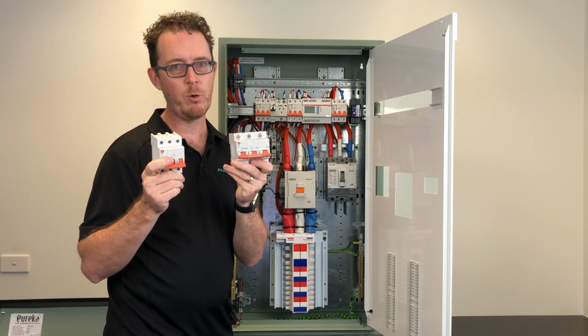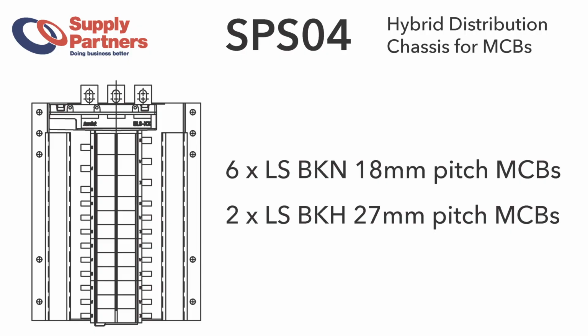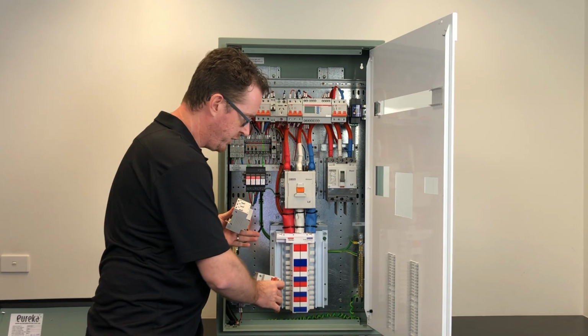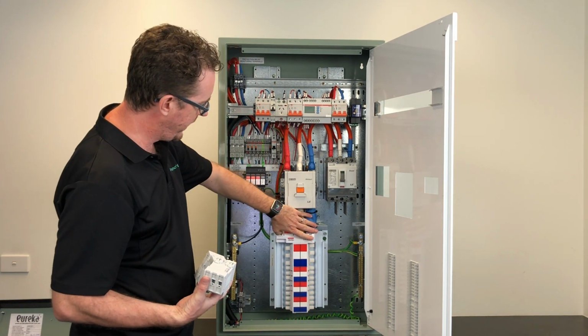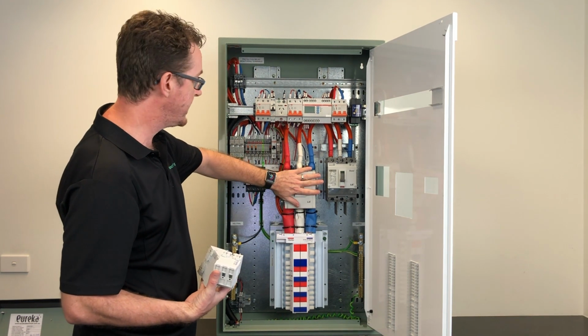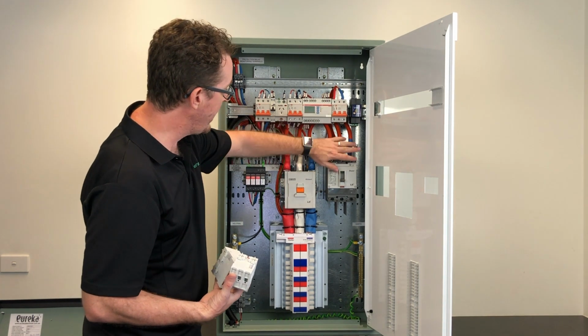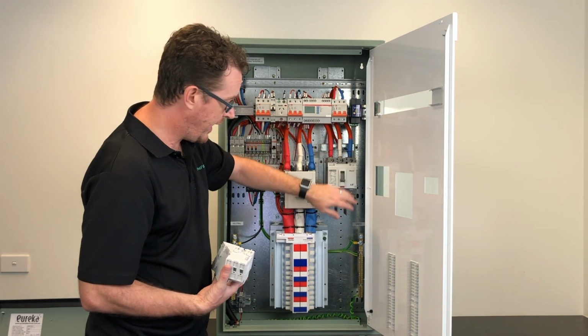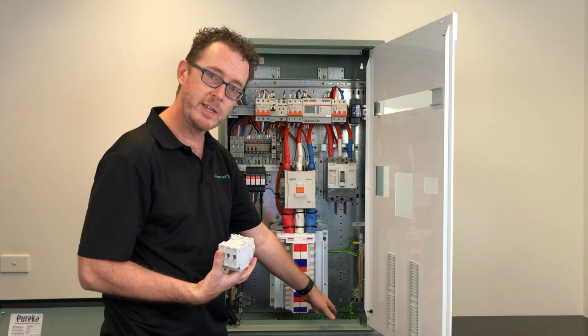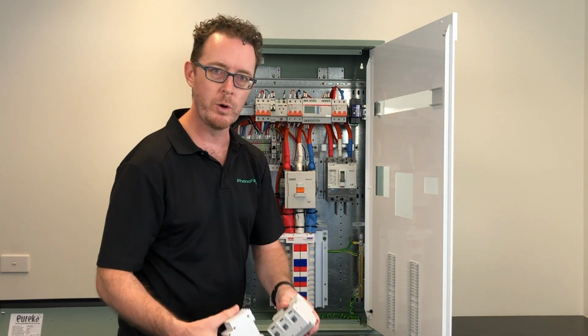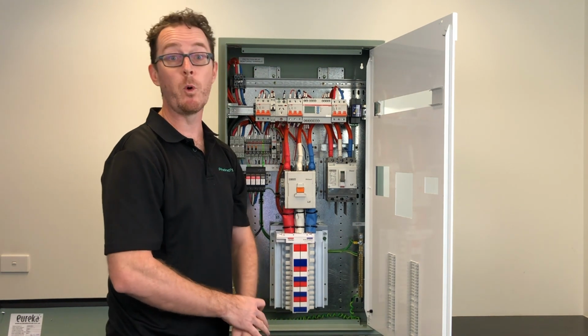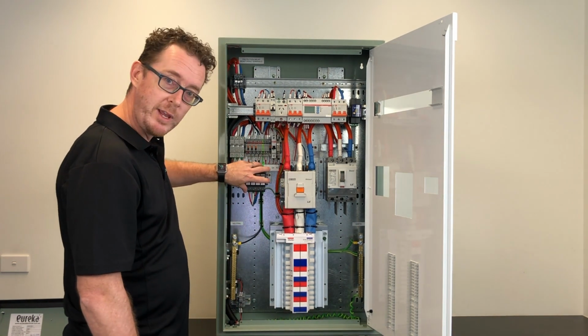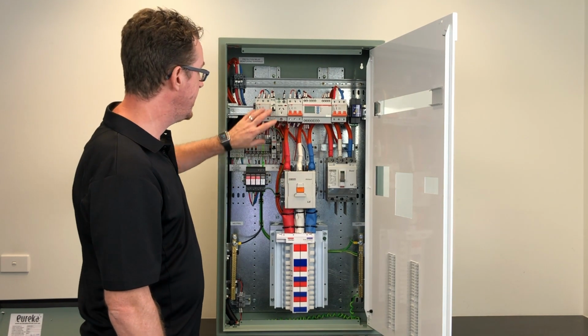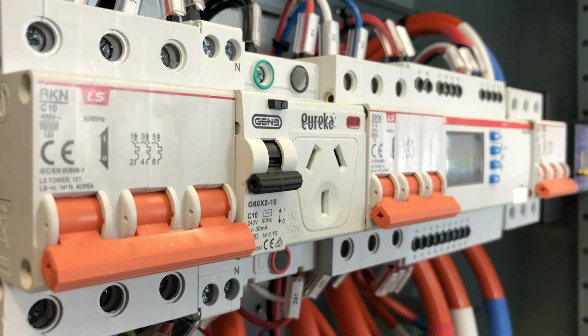All of these different configurations are achievable using the distribution chassis, where the circuit breakers go straight onto the fingers here. And then you can see that we have the busbars up to the contactor. They flow through around to the main isolator, and then from here you have your AC feed to your main switchboard, or the switchboard that you're connecting to. You can see we have the surge protectors here, all the other electronics, and there's a lot of clever thinking that's gone into this design.